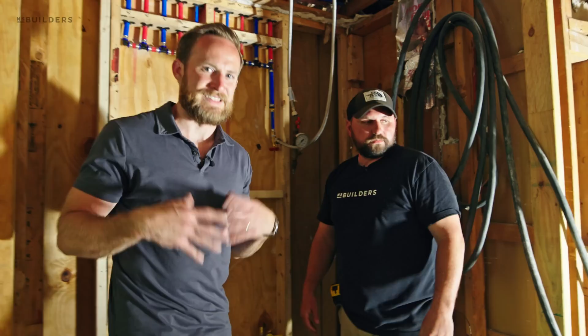And this ties into our main coming into the building. Remember, this is an existing one unit in a 4-unit building—we're in a brownstone in downtown Boston. So we're dealing with existing conditions, including a hot water source that serves the whole building. We have a hot water line coming in as well as a cold water line; we're not producing our own hot water.